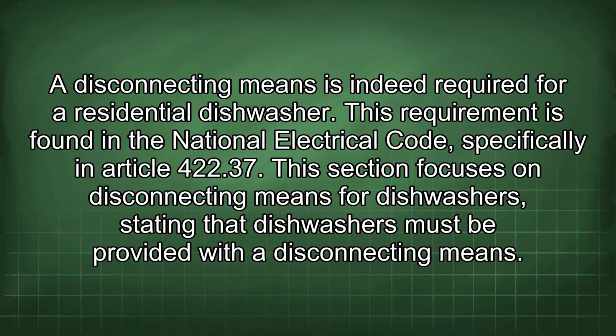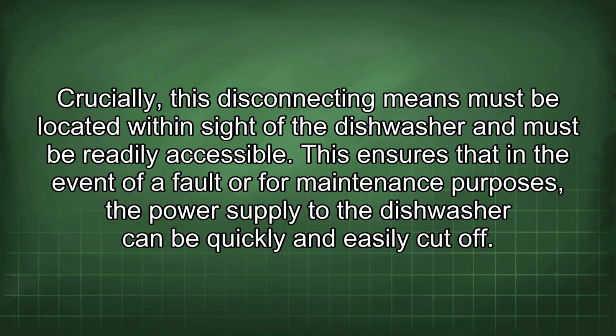A disconnecting means is indeed required for a residential dishwasher. This requirement is found in the National Electrical Code, specifically in Article 422.37. This section focuses on disconnecting means for dishwashers, stating that dishwashers must be provided with a disconnecting means. Crucially, this disconnecting means must be located within sight of the dishwasher and must be readily accessible. This ensures that in the event of a fault or for maintenance purposes, the power supplied to the dishwasher can be quickly and easily cut off.